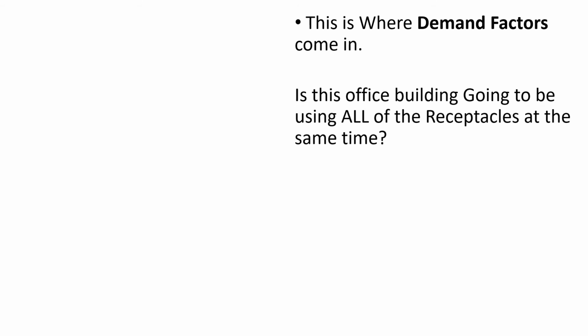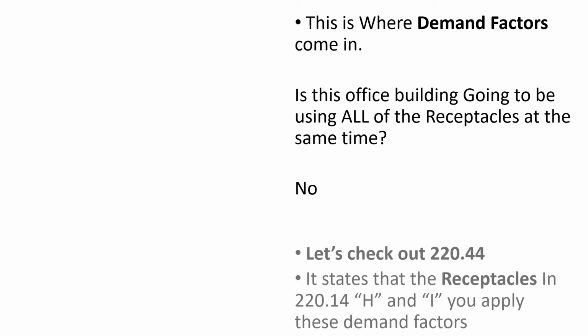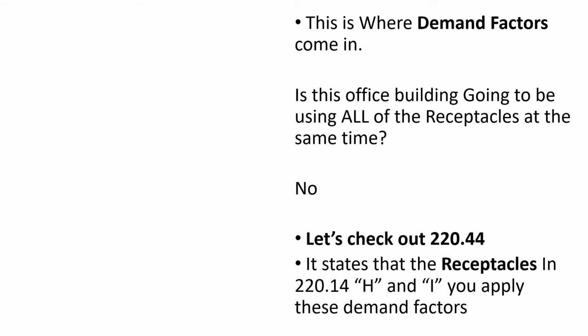This is where demand factors come in. Is this office building going to be using all of its receptacles at the same time? No. Let's check out 220.44. I want you to take a minute and we're going to read it and then check out its table. It states that for the receptacles in 220.14(I) and (H), you apply these demand factors.